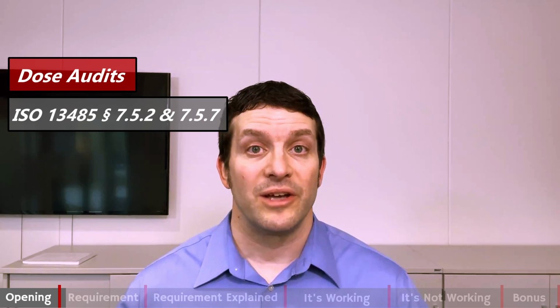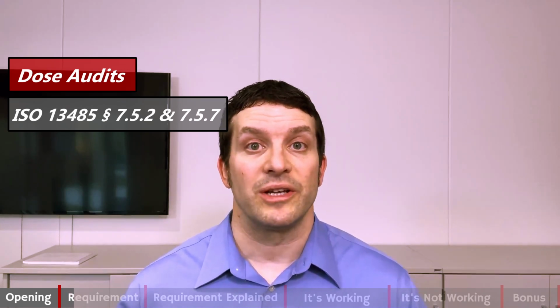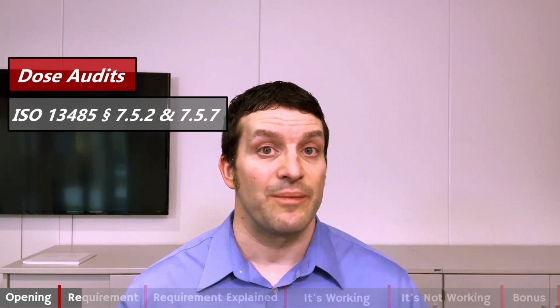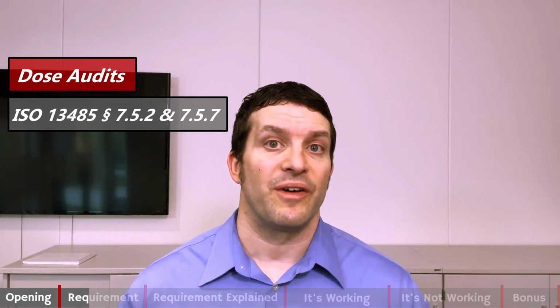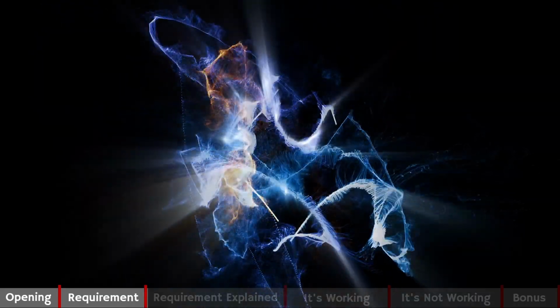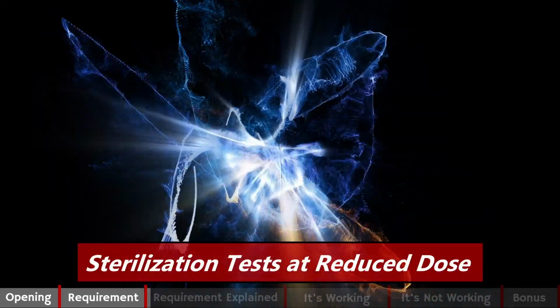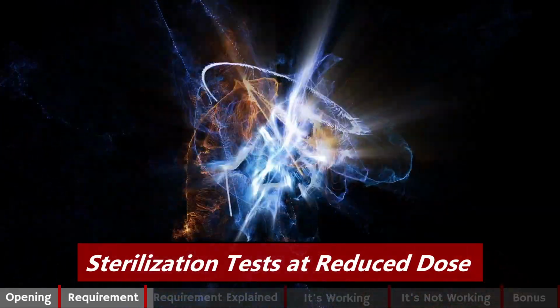Our topic, dose audits, is covered by 13485, sections 7.5.2 and 7.5.7. There is also a standalone ISO standard, 11137, Sterilization of Healthcare Products, Radiation, Part 2, Establishing the Sterilization Dose. Dose audits, in 5 words: sterilization tests at reduced dose.